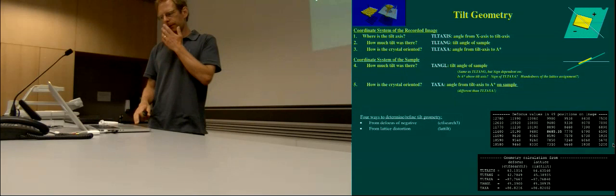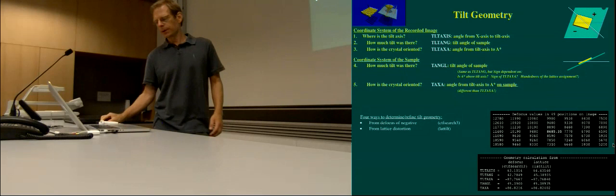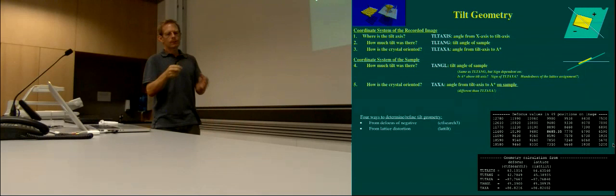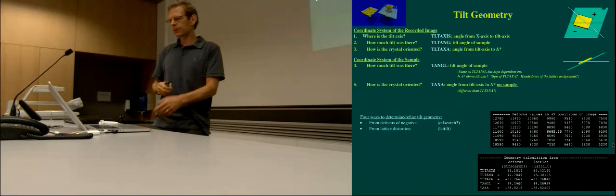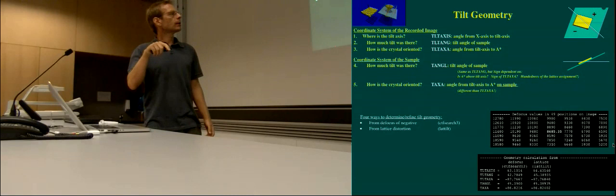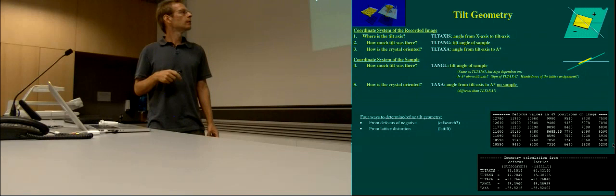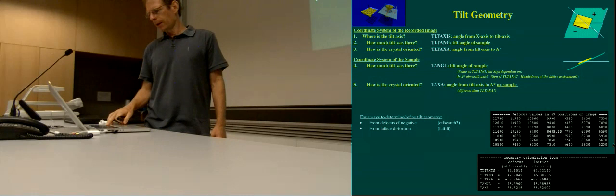Another way to find out the tilt geometry is from lattice distortions. When the crystal is tilted, the picture is shortened, and in Fourier space it's elongated in reciprocal space. That also gives you distortions of your crystal lattice. If you quantify these distortions precisely, you can find out what the tilt geometry is. This is done by a program that David Ager programmed — EMTILT — a long time ago.